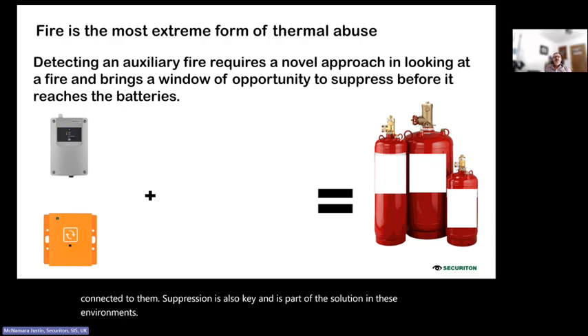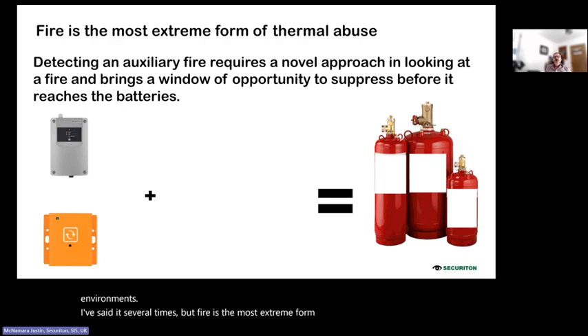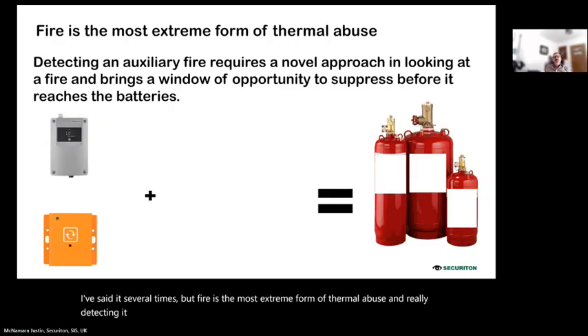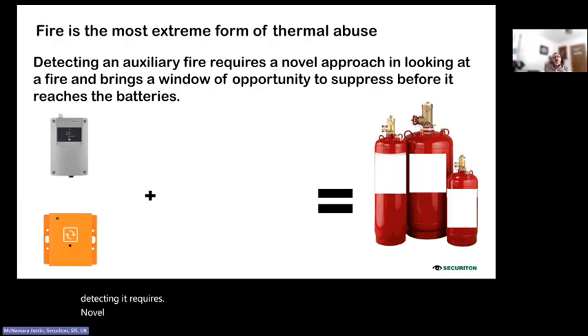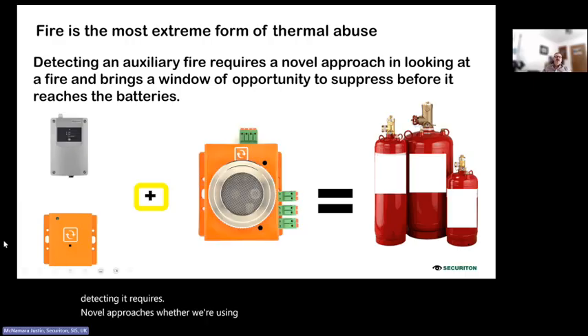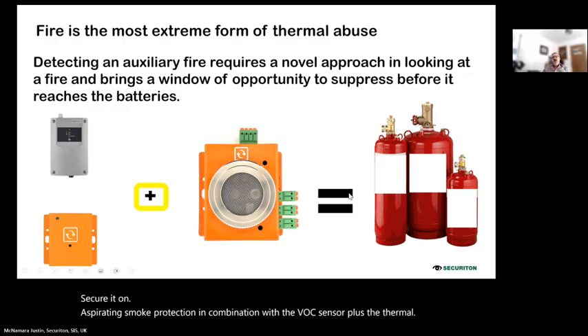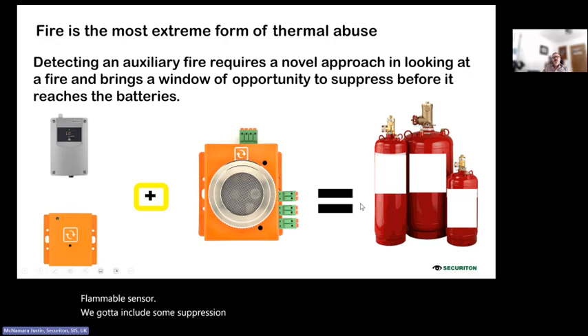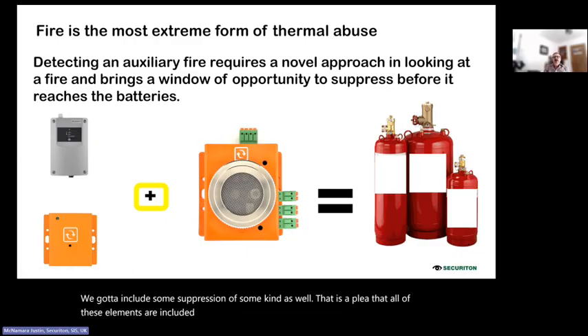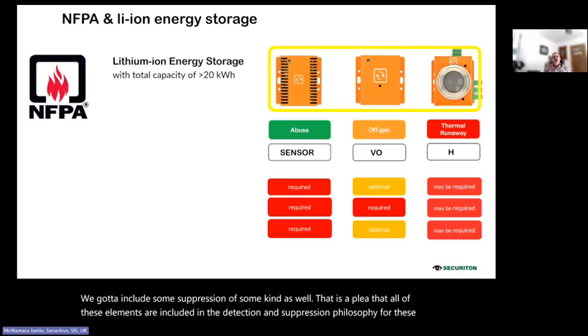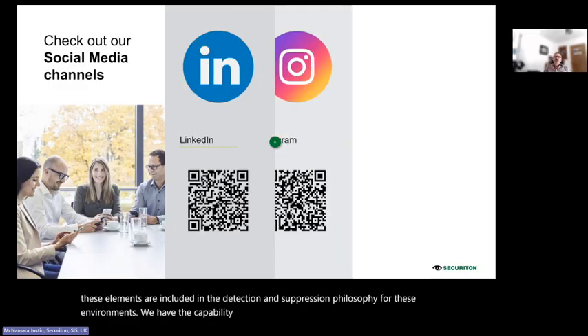I've said it several times, but fire is the most extreme form of thermal abuse, and really detecting it requires novel approaches. Whether we're using the Securiton aspirating smoke detection in combination with the VOC sensor, plus the thermal flammable sensor, we've got to include some suppression of some kind as well. That is a plea that all of these elements are included in the detection and suppression philosophy for these environments. We have the capability to provide all of the detection.